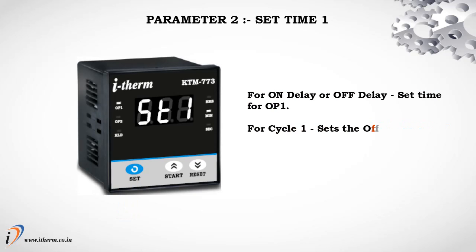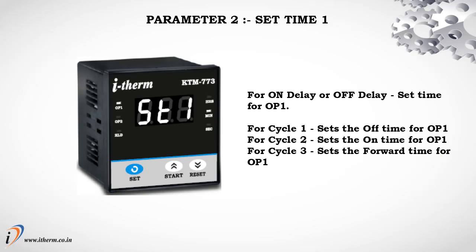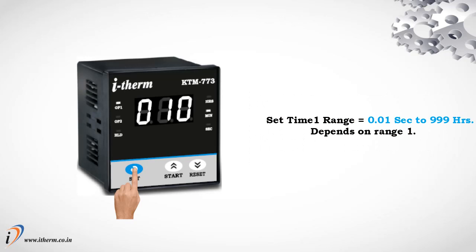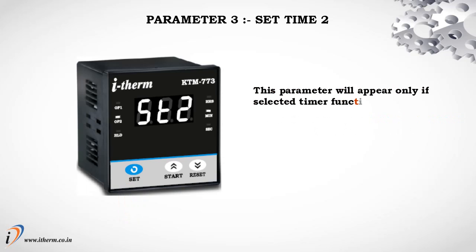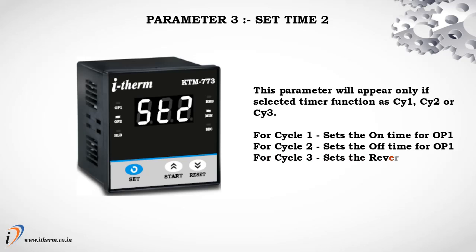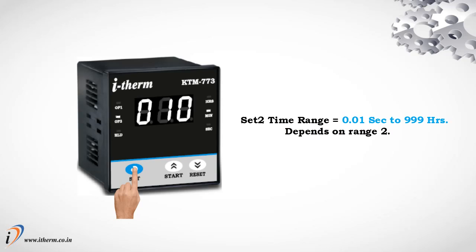Parameter 2: Set time 1. For on delay or off delay, sets the time for output 1. For cycle 1, sets the off time for output 1. For cycle 2, sets the on time for output 1. For cycle 3, sets the forward time for output 1. Parameter 3: Set time 2. This parameter will appear only if the selected timer function is cycle 1, cycle 2, or cycle 3. For cycle 1, sets the on time for output 1. For cycle 2, sets the off time for output 1. For cycle 3, sets the reverse time for output 2. Set time 2 range: 0.01 seconds to 999 hours, depending on range 2.